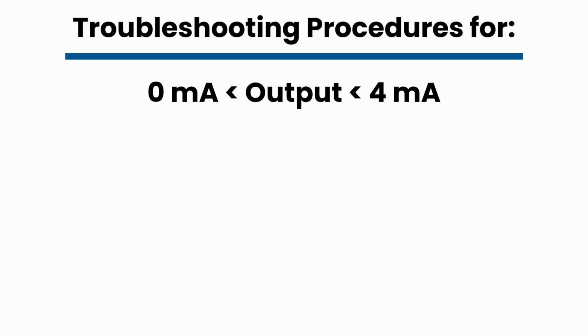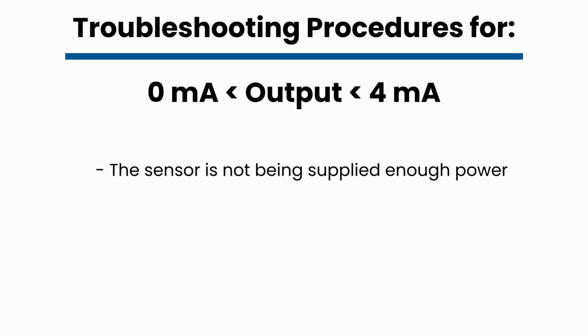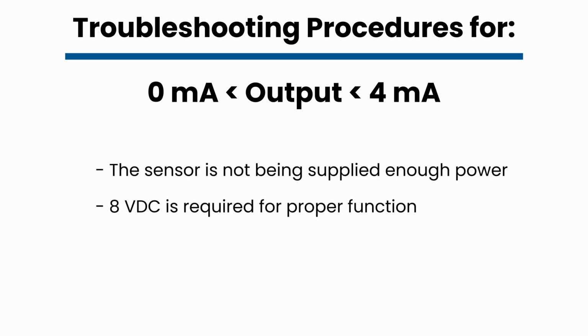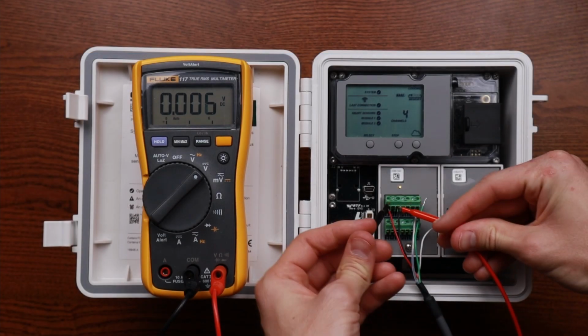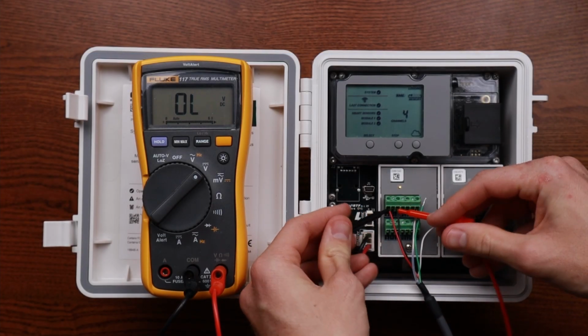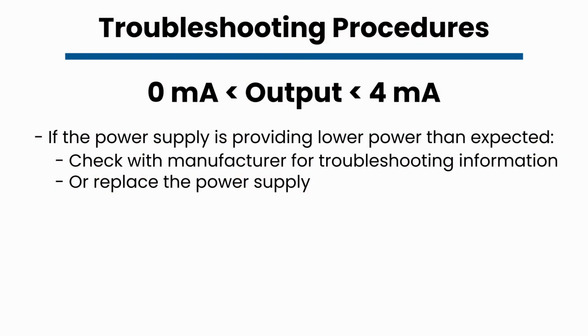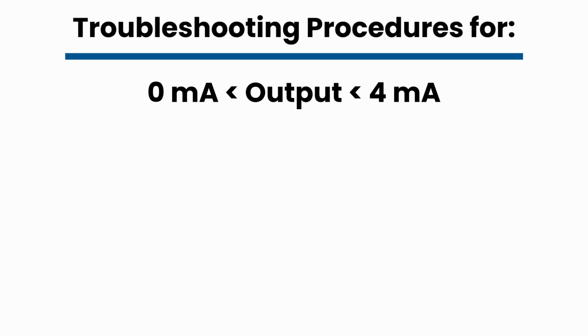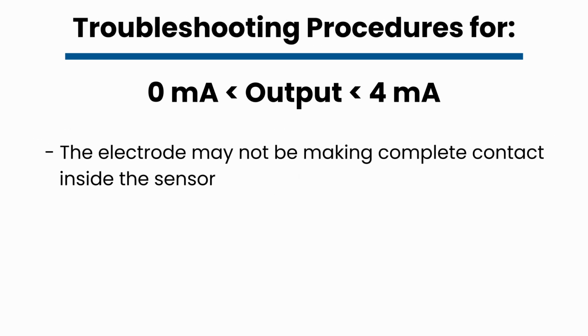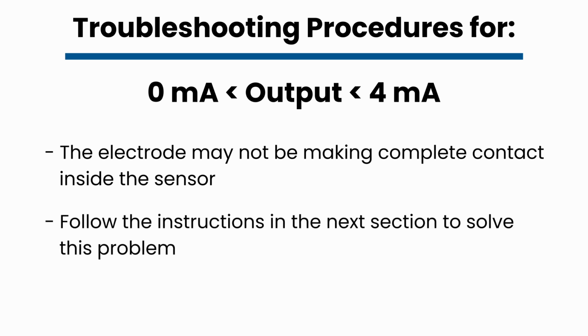If the output is between 0 and 4 milliamps, then the sensor is not being supplied sufficient power to function. The power supply must provide 8 volts DC or more. Check this by setting up a DVM and measuring the voltage across the red and black wires while they are being supplied power. If the power supply is providing a lower voltage than it should, then check with the manufacturer for troubleshooting information. The other possibility is that the electrode is not making complete contact inside the sensor. Follow the instructions for steady 4 milliamp output in the next section to fix this.